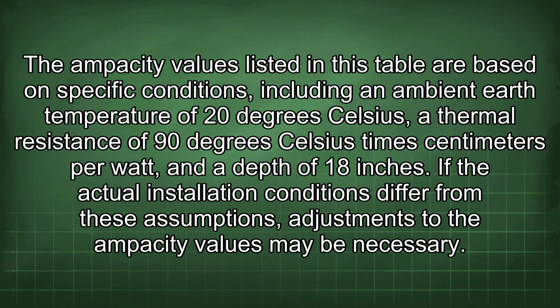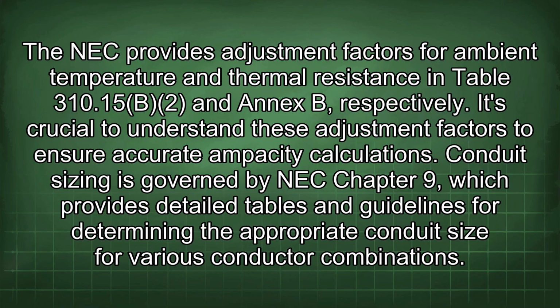The ampacity values listed in this table are based on specific conditions, including an ambient earth temperature of 20 degrees Celsius, a thermal resistance of 90 degrees Celsius times centimeters per watt, and a depth of 18 inches. If the actual installation conditions differ from these assumptions, adjustments to the ampacity values may be necessary. The NEC provides adjustment factors for ambient temperature and thermal resistance in Table 310.15(B)(2) and Annex B, respectively. It's crucial to understand these adjustment factors to ensure accurate ampacity calculations.